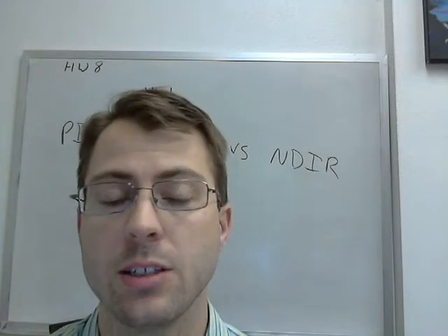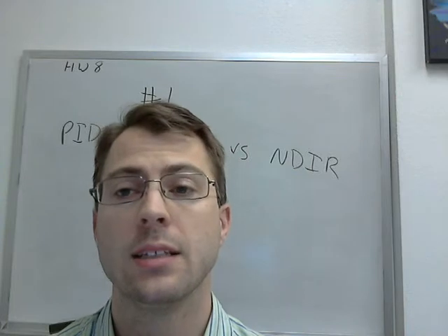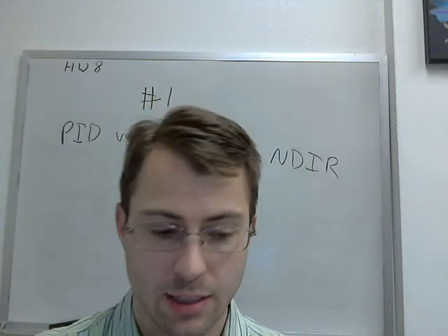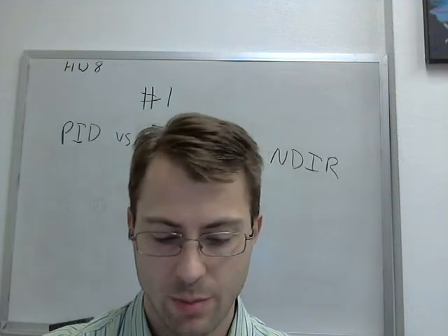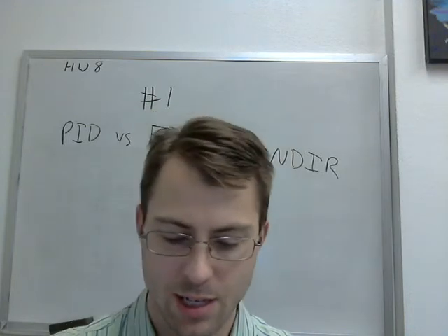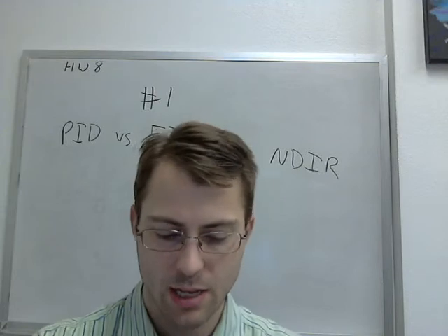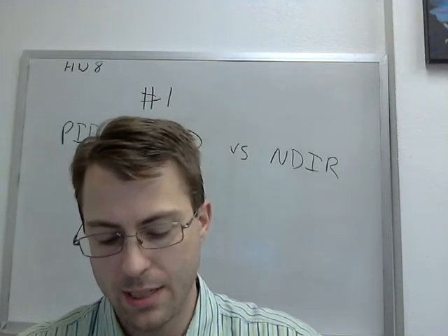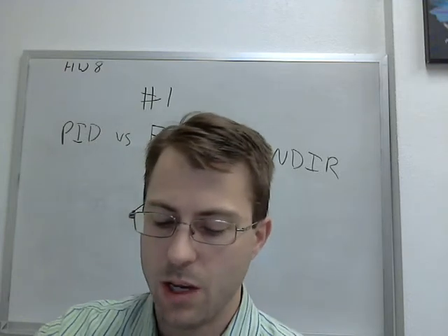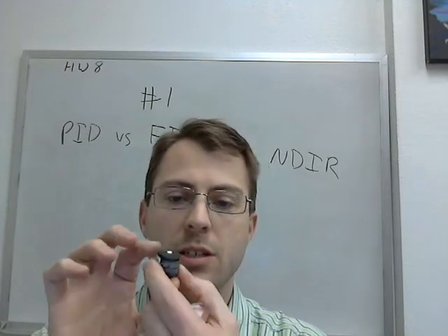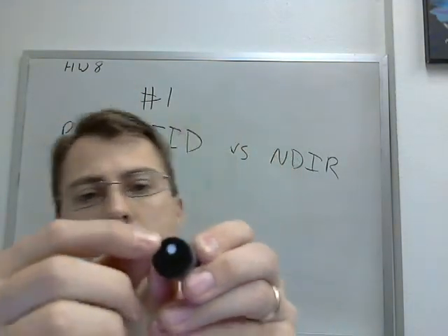The photoionization detector, the PID, has recently become very miniaturized, and I've got one here on my desk. I didn't actually set this up, but this is the size of a PID in most handheld 4 gas meters. This one is manufactured by Baseline Mocon. You can see this thing is small. And so the sensing cell is just below that white spot, and the whole thing is small.